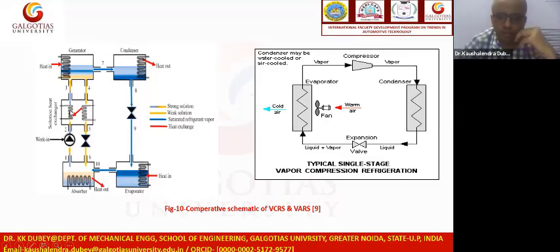What is the use of the heat exchanger? We will see through this return track. Now the rich solution is available in the generator. Here the heat source is available, 100 degrees C, 200 degrees C, as per the requirement. If we take ammonia, the boiling point of ammonia is minus 33 degrees C, so we don't need a high temperature. 50, 70 and 80 degrees is more than sufficient for the ammonia plant. So if ammonia is used, we can use 90 degrees as the generator source. Now the ammonia will convert into superheated vapor and pass through the condenser.